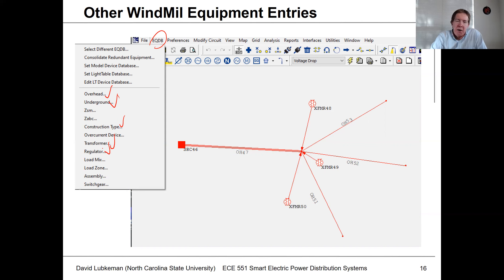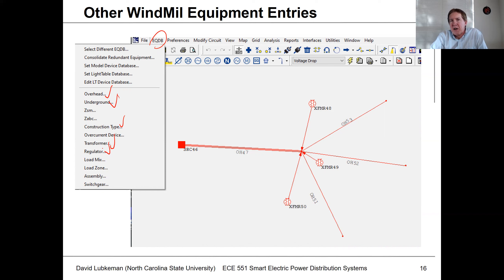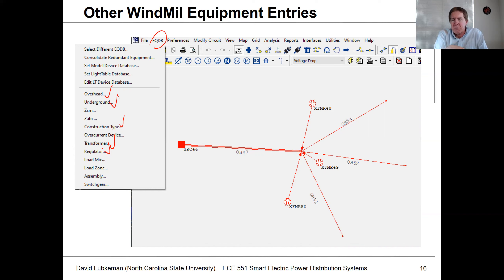You might want to take some time to look at these different tables. In a program like Milsoft, if you go up to EQDB and pull down the menu, you can get all the data on overhead or underground construction types, different transformers, or different regulators — all stored in a series of tables. If you give me all these tables, that's a complete description of a circuit. For the project results, I'll ask you to dump these tables out because by looking through them I can quickly tell whether you built the circuit properly.